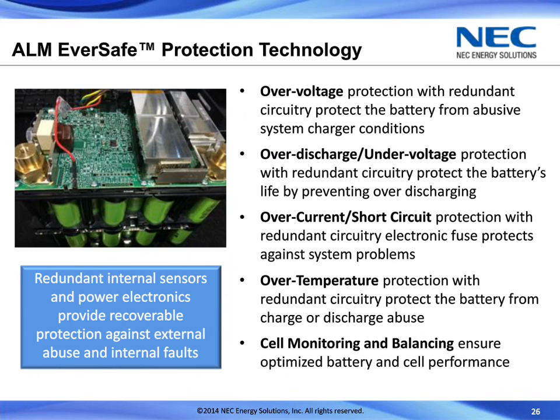And then finally, I'd like to highlight what we call our EverSafe protection technology, which is our BMS that provides the utmost level of protection and safety for lithium-ion batteries. We protect against overvoltage, over discharge and under voltage, over current and short circuit protection, over temperature, and do all the typical cell monitoring and balancing required of lithium-ion batteries. We do this with full redundancy. We have redundant sensors, redundant power electronics to provide recoverable protection against external abuse and internal faults. So not only do we protect, but we also automatically recover from most of these faults. So if that fault is cleared, the battery is not disabled, but it'll come back into use when any kind of external event that may have caused the battery to go offline to protect itself and the system goes away.